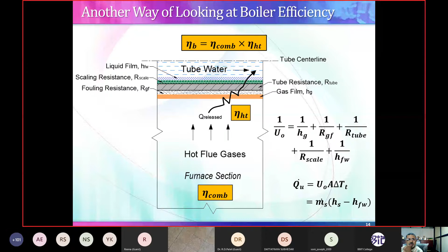Next. Use advanced fuel additives. These additives will improve the combustion by catalytic effect. So this will improve my combustion efficiency and decrease m dot f. Second, this will also help in reducing fouling of heat transfer, so this will increase my heat transfer efficiency. This will improve my steam generation, and that will result in improvement in eta B.